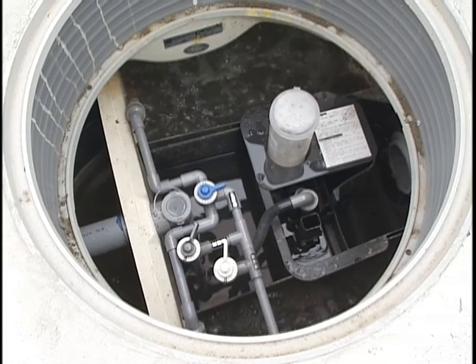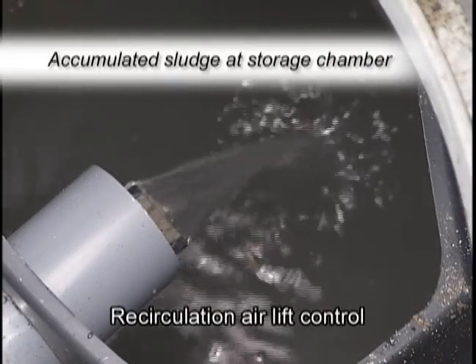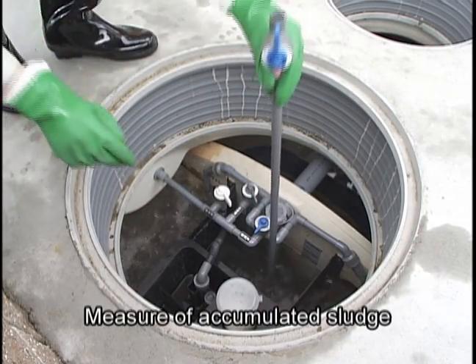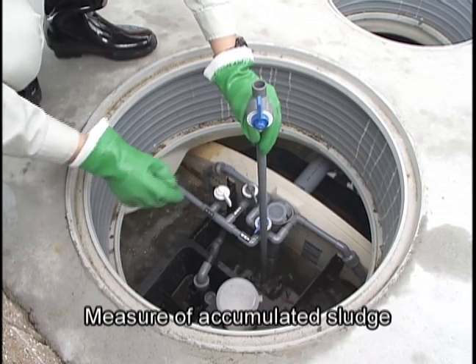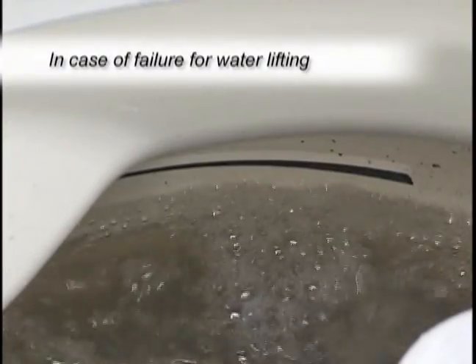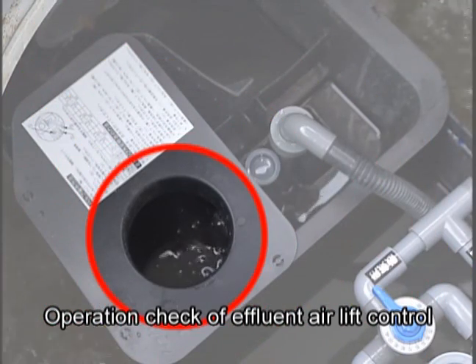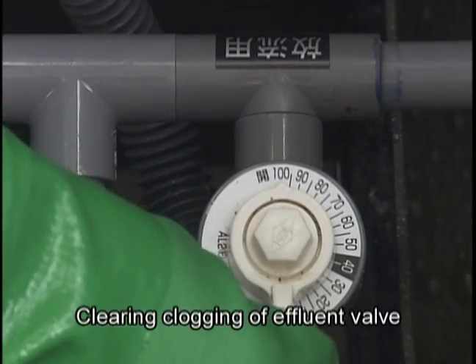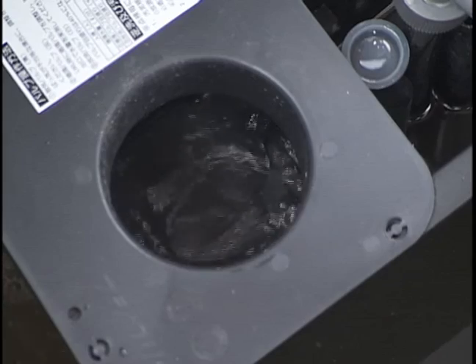If you find a mass of biofilm on the wall of the tank, remove it manually with a brush or cleaning tool. If you find accumulated sludge in the clarification chamber, ensure that the recirculation airlift pump is functioning properly, transferring sludge and processed water back to the sedimentation chamber. If no water is being pumped up through the discharge airlift pump while the water level is above the low water level line, then using a cleaning brush, clear any clogs in the effluent airlift pipe. Also clear any possible clogs in the effluent valve itself by opening and closing the valve several times at every inspection.